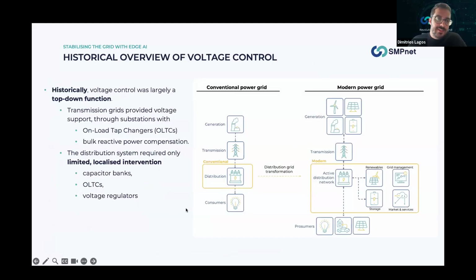So, voltage control. Let's do a deep dive on how this is performed in power systems. Historically, in legacy power systems, prior to the energy transition that we are experiencing over the last decade, voltage control was mainly a top-down function. That means that the main party responsible for performing the voltage control was the transmission system operator. So transmission systems provided the voltage support through on-load tap changers at transformers and through bulk reactive power compensation, which means capacitor banks and reactors connected when we needed reactive power provision.